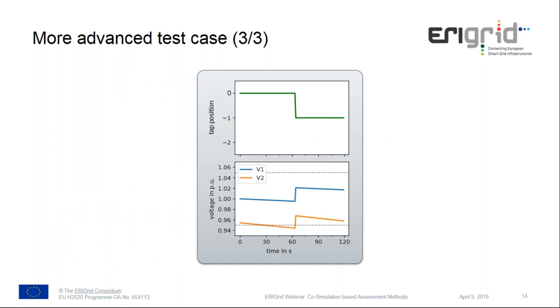Just as a teaser, basically what the results show you is here you see what you would usually expect. So you can see in the lower figure the voltages from the 2 meters in this test setup, and you see that after some time one of the meters, the voltage drops below the threshold, below the operational threshold, and then on the upper figures you see that the tap position of an on-load tap changing transformer changes accordingly.